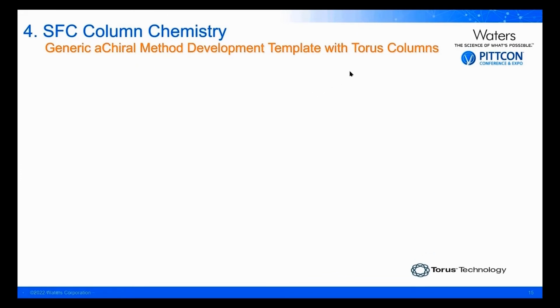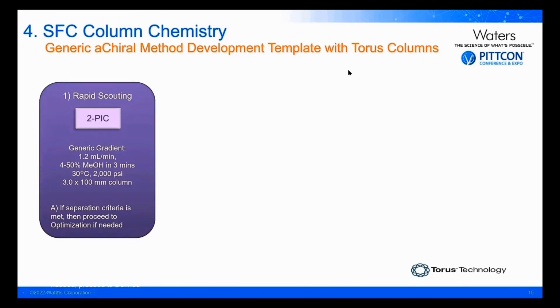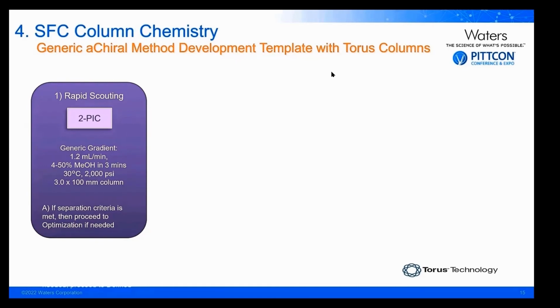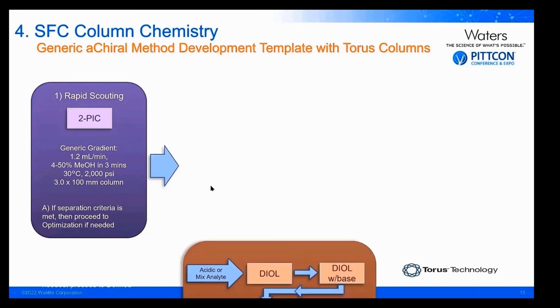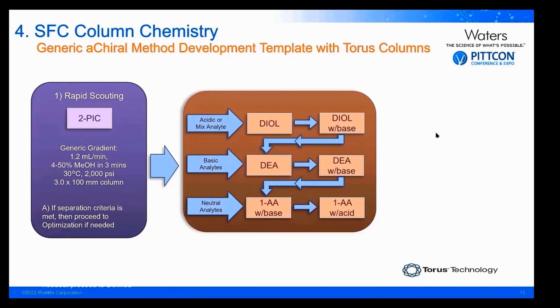When you create an analytical SFC system and chemistry, you want to give your customers a specialty template so they can develop their own method. So this is the generic template that we use using the Torus brand 2-PIC. It's 1.2 mils a minute, 4 to 50% methanol in 3 minutes, and then 30 degrees C, 2000 psi back pressure.